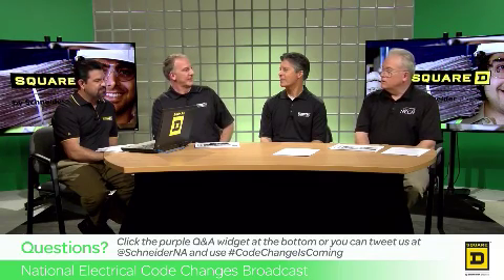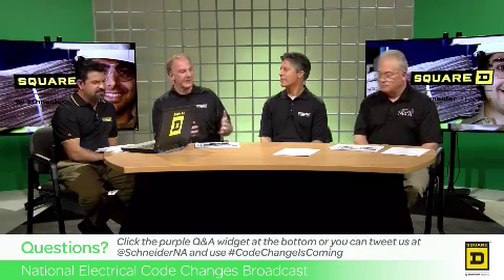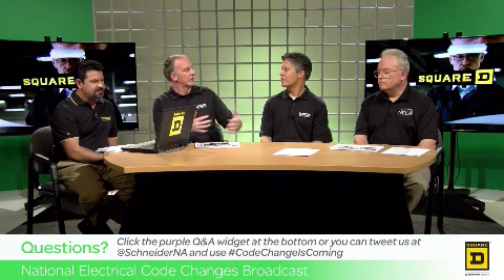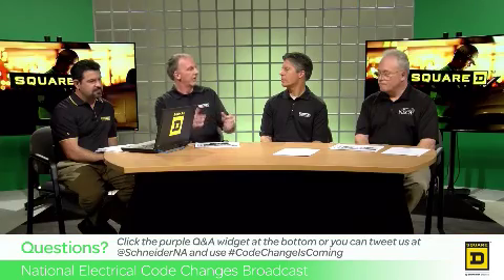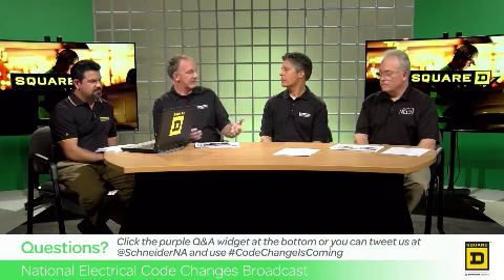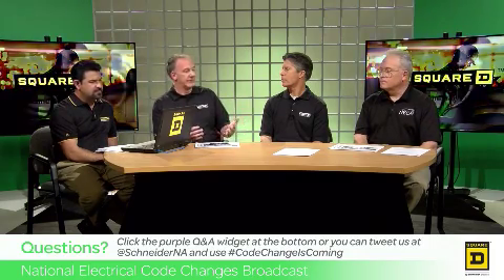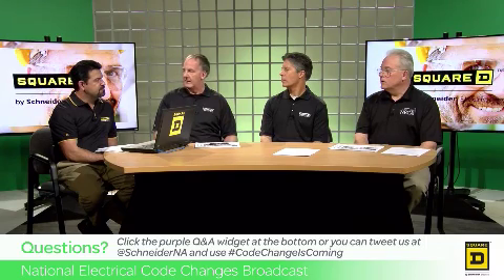That's a pretty broad discussion, I've got to say. From healthcare to emergency systems, from a code requirement perspective, we've got elevators, there's a whole list of those in the code where there's a selectivity requirement in place today. As far as a marking requirement, there's not a marking requirement. I think the new 110.41 probably provides a mechanism for that information to be communicated so that people know where the settings go. They can be verified by the installer, verified by the enforcer or the inspector, and provide that communication piece. I don't think there's a specific marking requirement, but there are various areas, and we'd get into a pretty extensive discussion if we jumped into each one, which I don't think we necessarily have time for at this point.